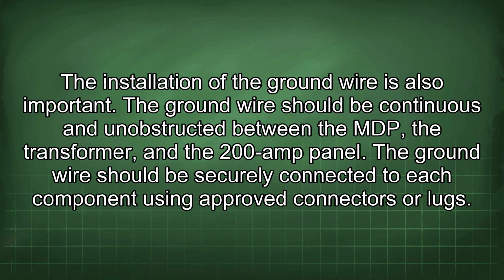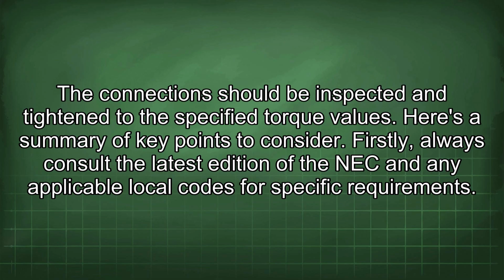The installation of the ground wire is also important. The ground wire should be continuous and unobstructed between the MDP, the transformer, and the 200 amp panel. The ground wire should be securely connected to each component using approved connectors or lugs. The connections should be inspected and tightened to the specified torque values.